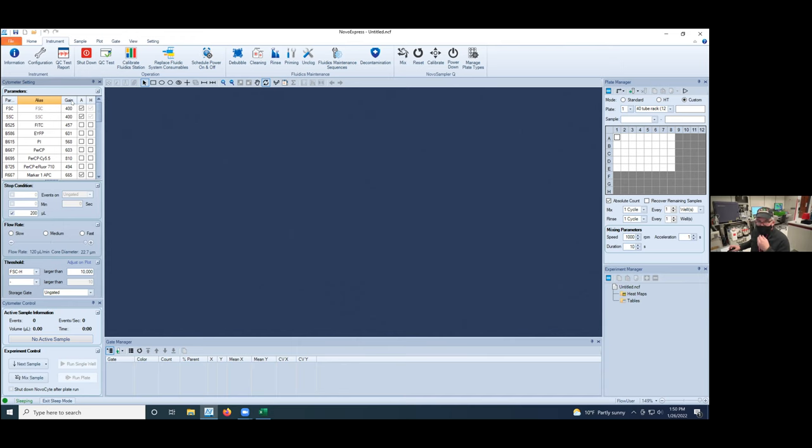The other thing I'm going to recommend is resetting the gains before you run your acquisition. The gains are set by the manufacturer. Essentially, what they did is run 8-peak beads, so a series of beads that have 8 different intensities. The gain that provided the best separation is the one that they use here. So that's the gain where you should have good separation between your positive and negative fraction.